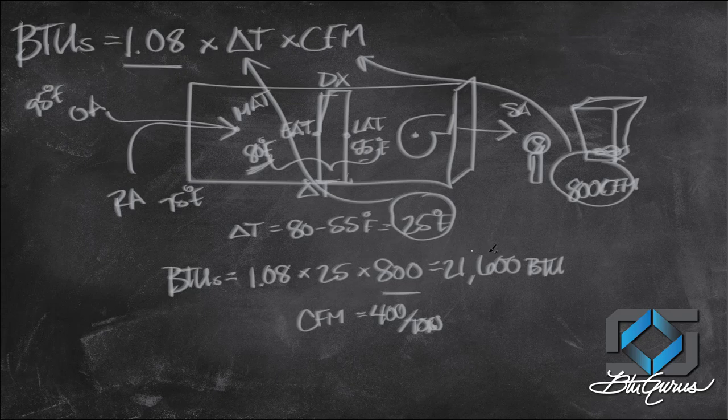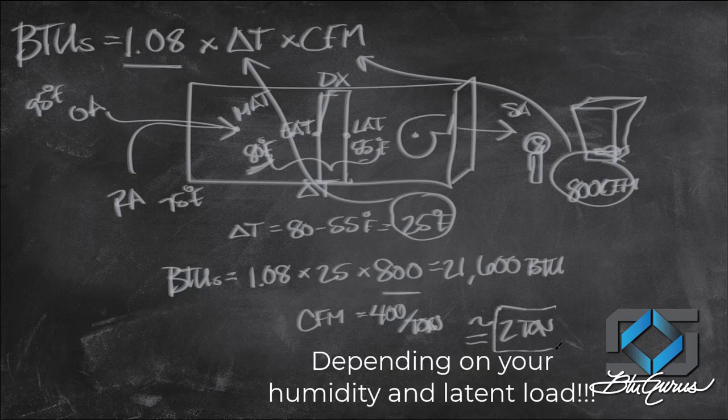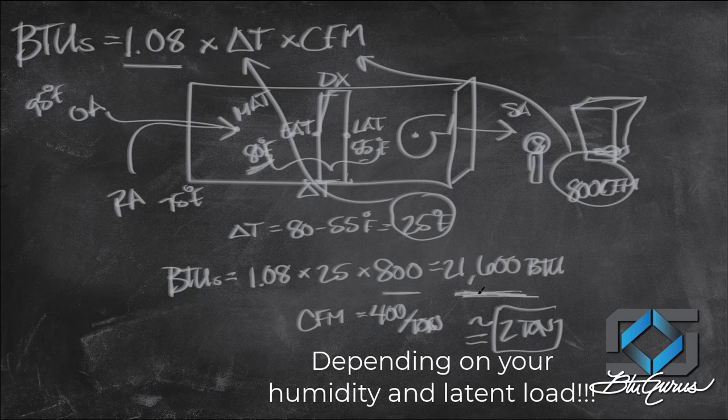If I'm doing 800 CFM, that would end up approximating the unit to be a two-ton unit. But because I used this example, I also wanted to show you where that rule of thumb usually actually comes from, and that's a targeted delta T.